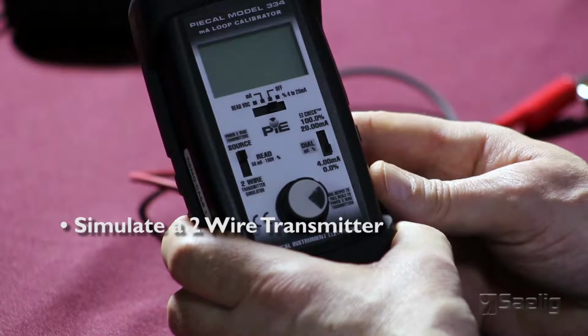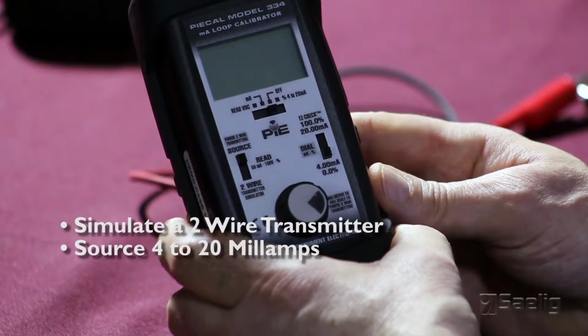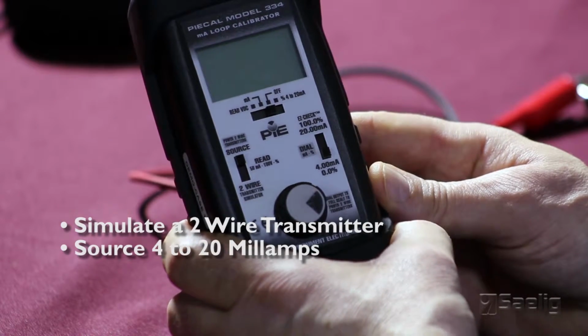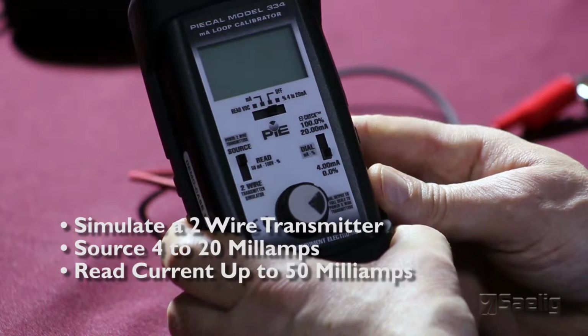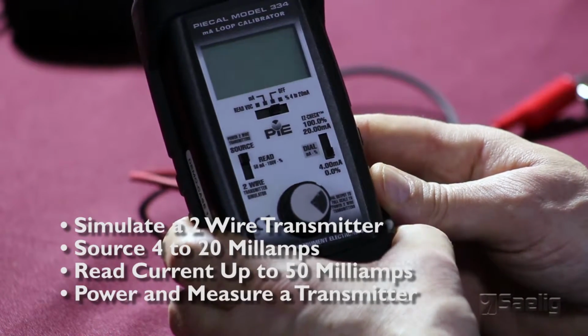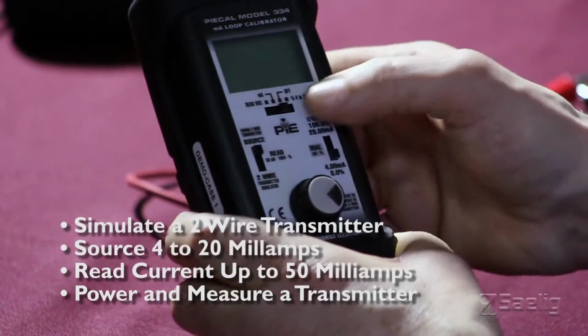Today I'm going to talk to you about PIE's line of milliamp and voltage loop calibrators. Our model 334 is our milliamp calibrator, which has been designed as a direct replacement for the Altek 334A. With this calibrator you can simulate a 2-wire transmitter, source anywhere from 4 to 20 milliamps, read current up to 50 milliamps, and also power and measure a transmitter.